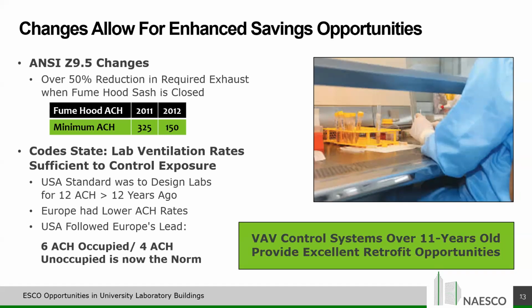That's a big change. And the next item isn't so much a code change as it is a design practice change, or an industry standard change. As I mentioned, when it comes to ventilation rates, the code states that it shall be sufficient to control exposure. Well, that's pretty gray. It can be interpreted a lot of different ways. And 10, 12 years ago, most design engineers were designing to 12 air changes per hour around the clock. It was no occupied, unoccupied. It was just 12 air changes per hour or more. During the same time, Europe was much more progressive. They were at 6 air changes per hour occupied, 4 air changes per hour unoccupied. And they were doing that for years and years.